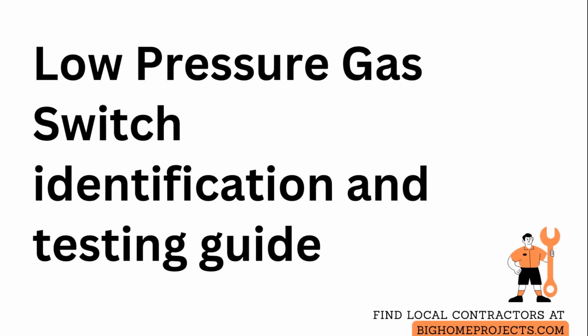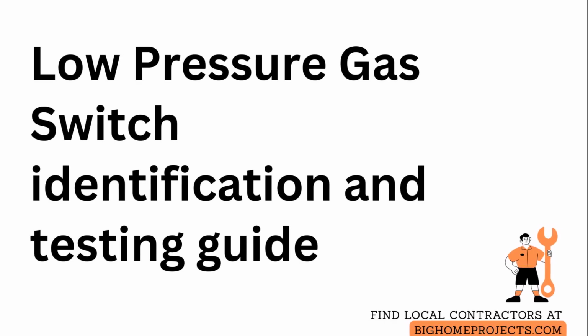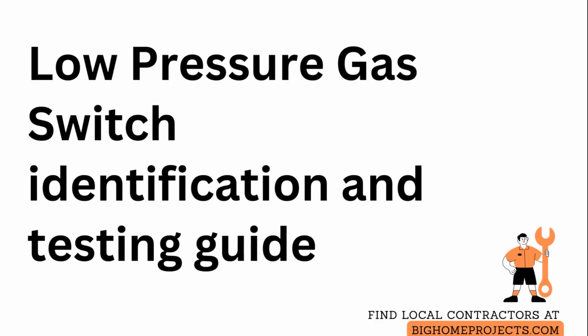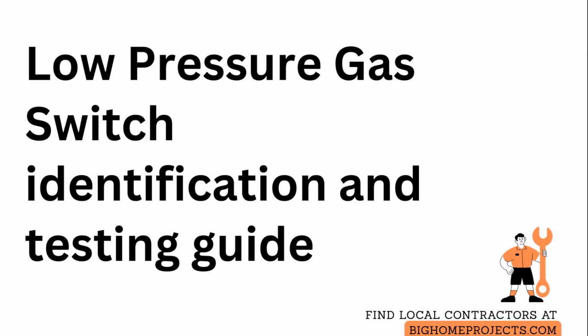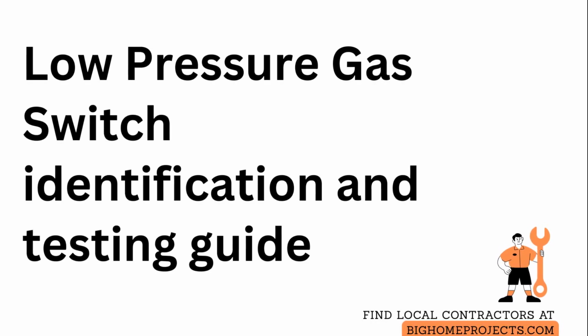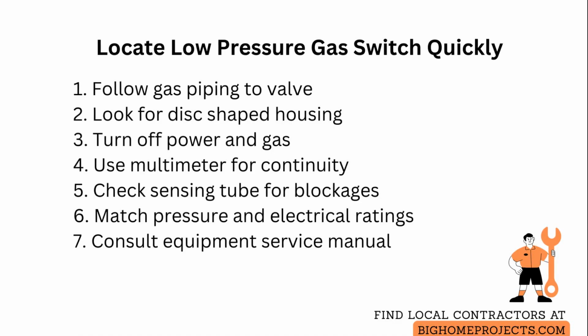The low-pressure gas switch is typically mounted on or adjacent to the gas valve assembly and looks like a small disc or round sensor with 1 or 2 thin wires attached. Locate the switch by following the gas piping to the gas valve and nearby control block.